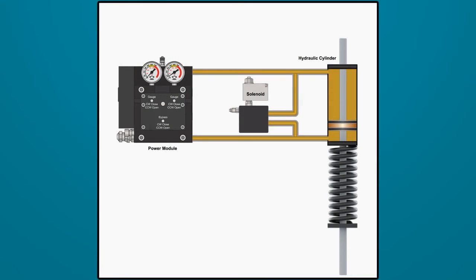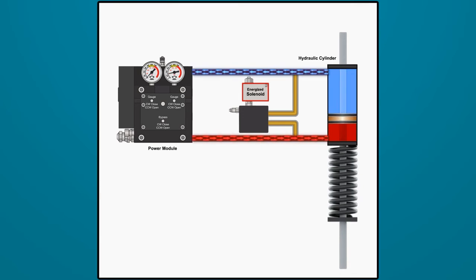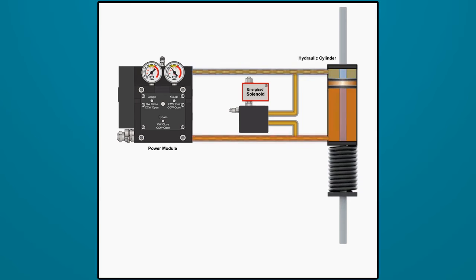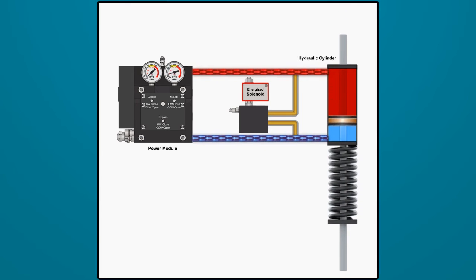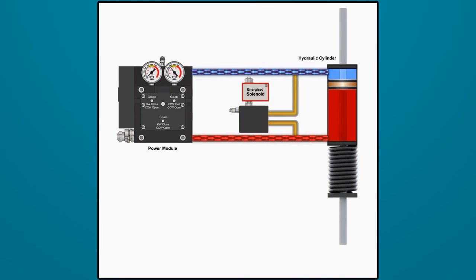During normal operation, the solenoid is energized to remain closed. In this state, the spring compresses and decompresses as the actuator extends and retracts while positioning the valve.